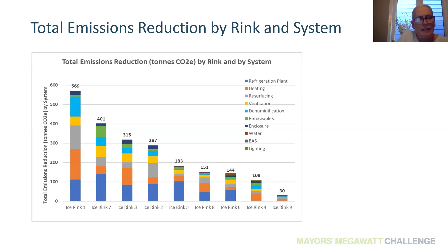In terms of high impact measures, we found the measure with the most impact in terms of greenhouse gas reductions is adding heat recovery to the existing refrigeration plant. The average emission savings from this measure was 89 tons, almost double the next measure, about a 34% average emission reduction.